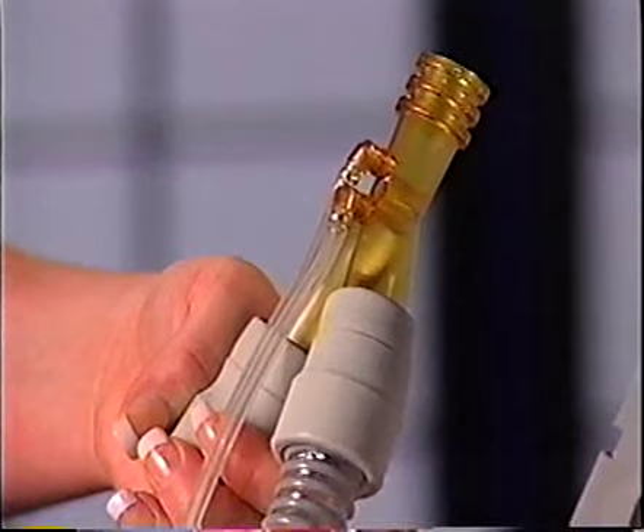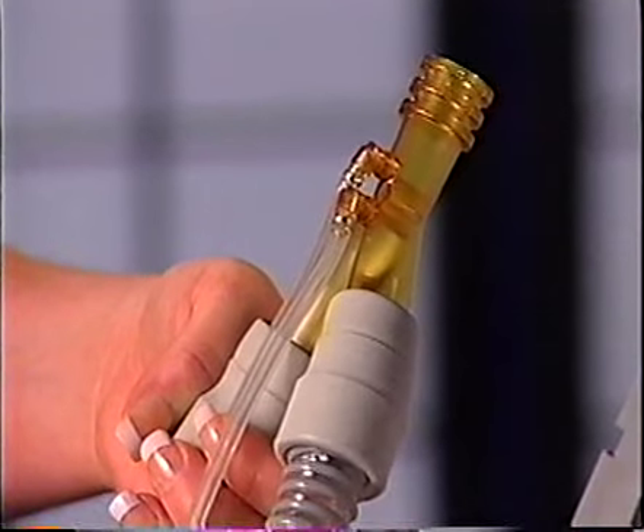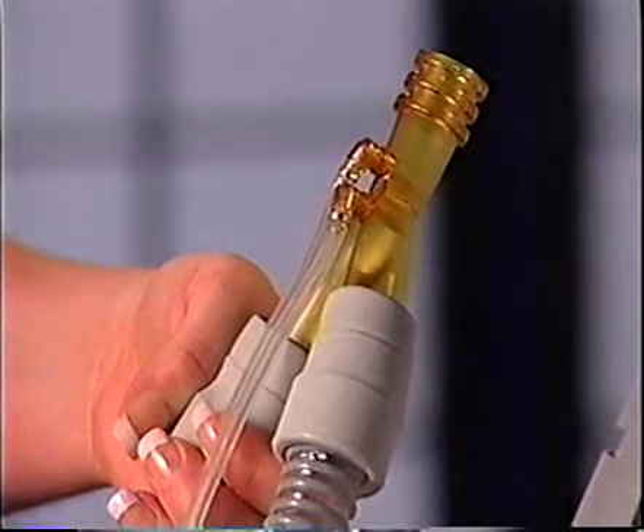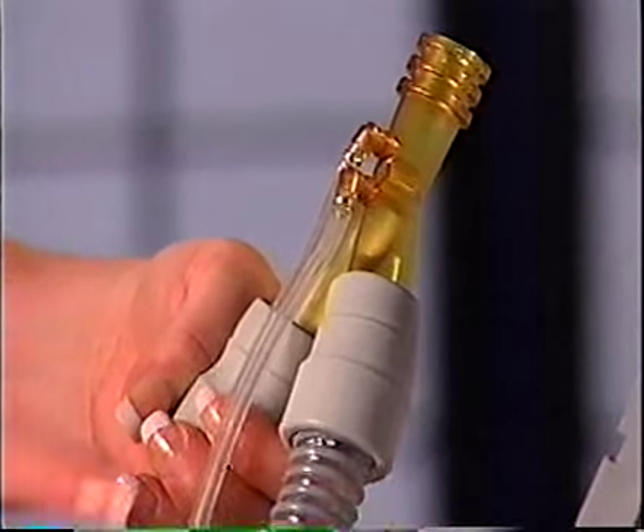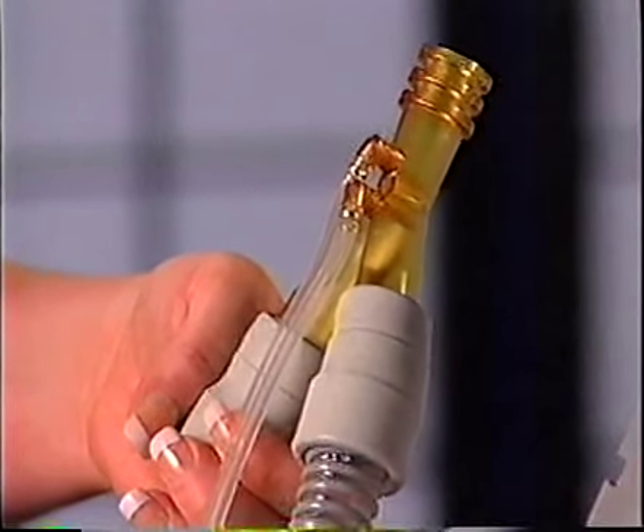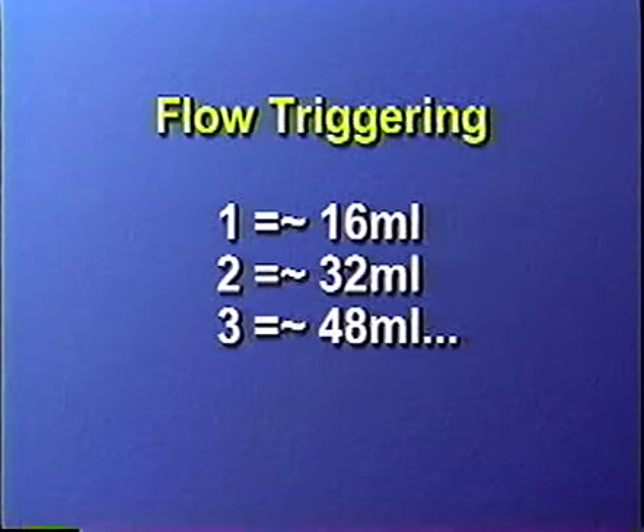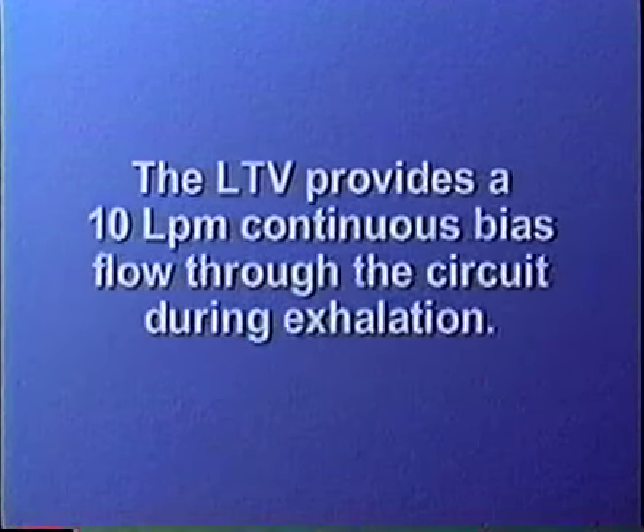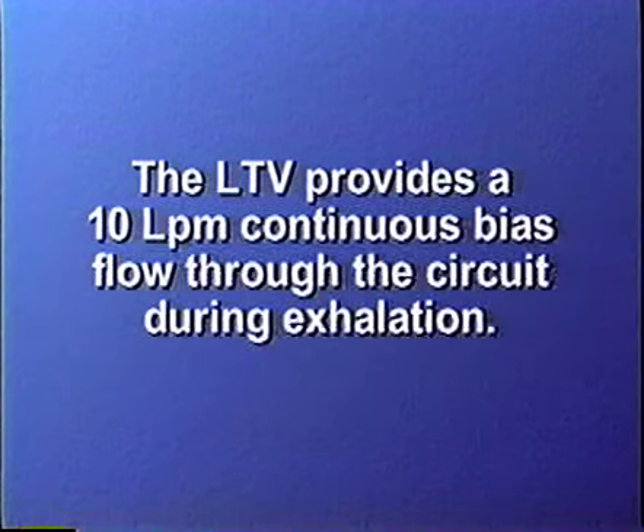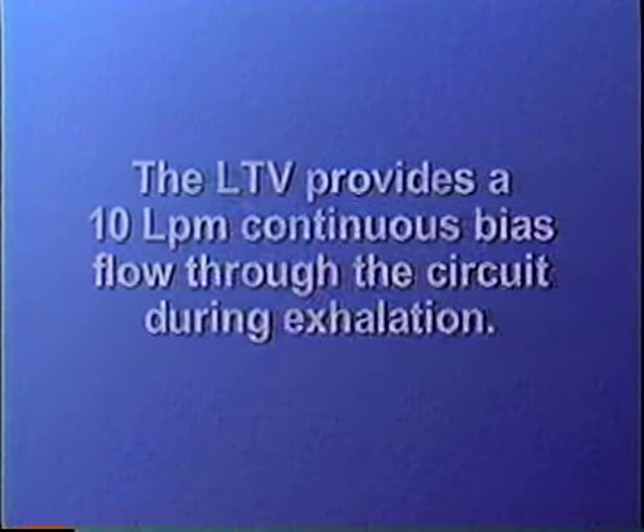The LTV is flow triggered with a backup pressure trigger at -3 centimeters of water pressure. The ventilator will trigger a breath when the flow passing through the flow sensor exceeds the sensitivity setting. This chart shows how sensitive the LTV is. A sensitivity of 1 means that the patient can trigger a breath with a draw of only 16 milliliters per second. A sensitivity setting of 2 means that the patient can trigger a breath with a draw of only 32 milliliters per second, and so on. Note that the LTV has a 10 liter per minute continuous flow through the circuit during exhalation.